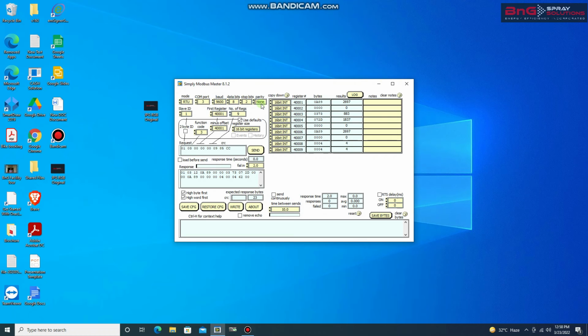So there will be 9 registers which the oxygen analyzer will be sending to the Modbus master, which the Modbus master will read. So in this case, the first register begins at 40,001, so we provide an offset of 40,001 as well. And you see, we can send continuously the data at 10-second intervals or 30-second, or as you set it. For this demonstration, we'll just send it once and you will see how it works. So we press the send button and the response happens in 0.4 seconds. And here you see the results of whatever the oxygen analyzer has sent to the registers.